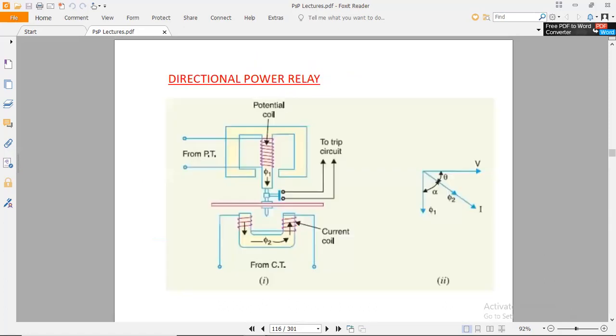Further, we are moving towards the next aspect of directional relays. Before that, we discussed the non-directional relay, and now we are discussing the directional power relays and how they are energized by the magnetic coil. First, we provide the potential coil, which has a set of tappings in the set of coils from PTs, which provide the flux phi 1 from one set of coil. Further, when it energizes, it provides the contact to make the tripping circuit.